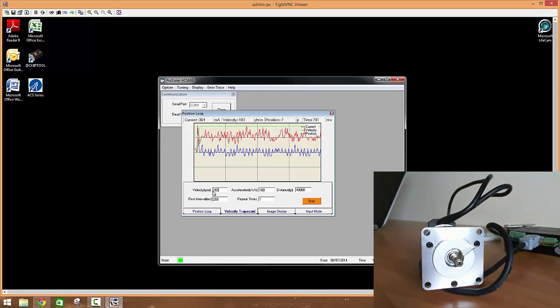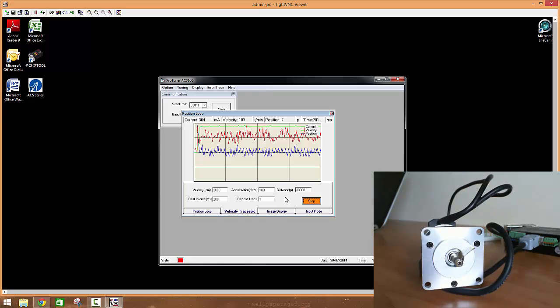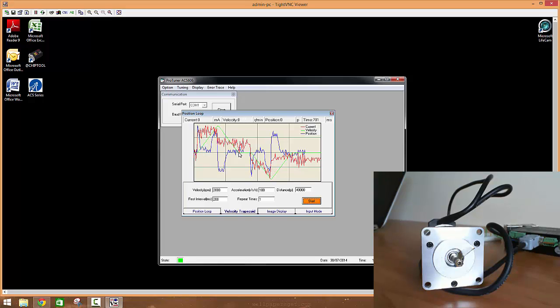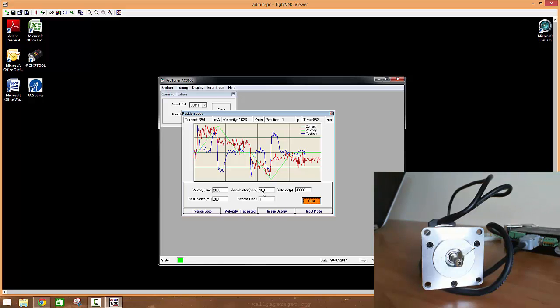When you want to hit, say, 2000 RPM and you only allow this acceleration within this given distance. Now that looks great, but it actually isn't, because if we go up here we see that our velocity has only hit 1825. We were ramping up very slowly and then we ramped down. Acceleration was all over the place, then we have that rest interval that goes in between.